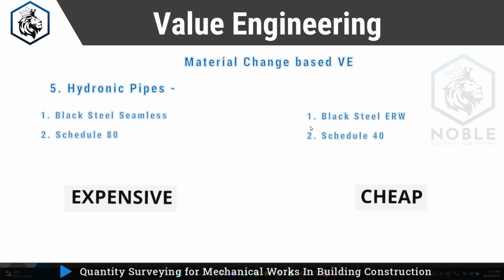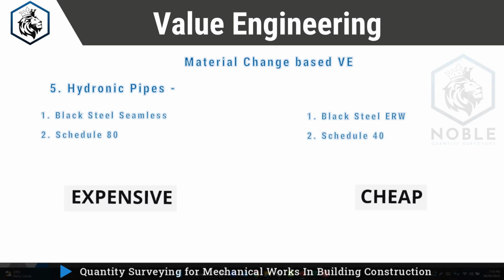I'll tell you the difference between these two - it's almost 40 to 45% in cost. For 20mm black steel ERW pipe, it costs only around 12 or 13 dirhams per meter, while black steel seamless pipe costs around 21 to 22 dirhams per meter. So this is the cost difference you can save. This is value engineering you need to use - if you see any black steel seamless pipe, it can be converted into black steel ERW pipe, because seamless pipe is recommended for marine applications and rig projects, but black steel ERW is used for common residential buildings.